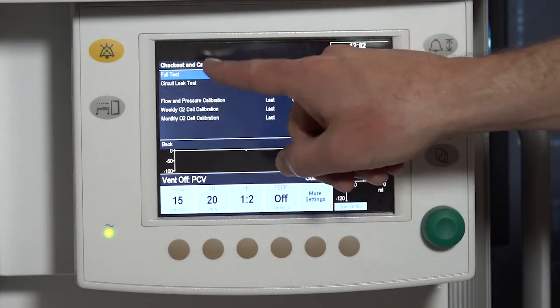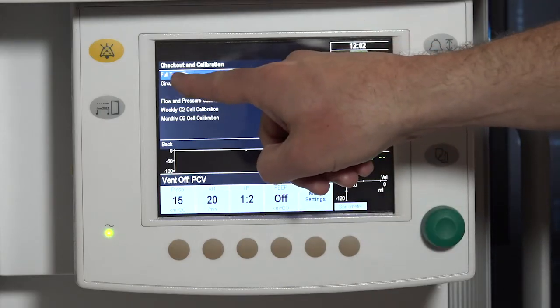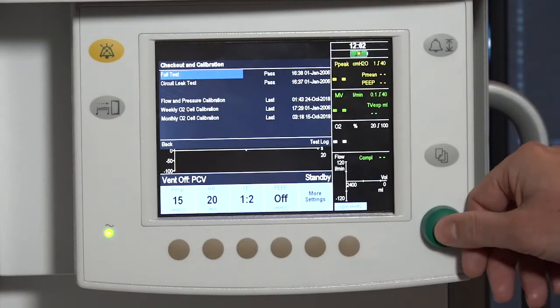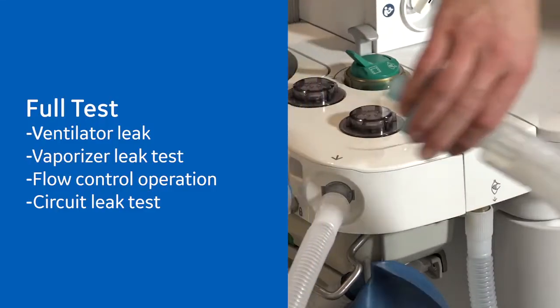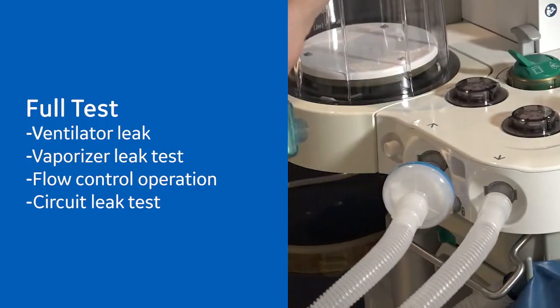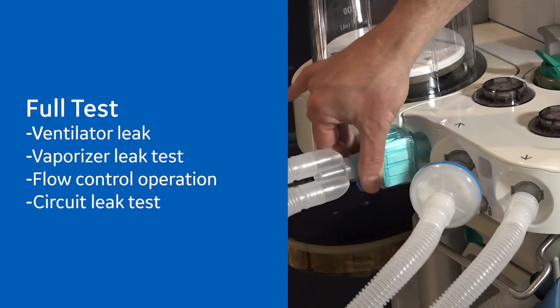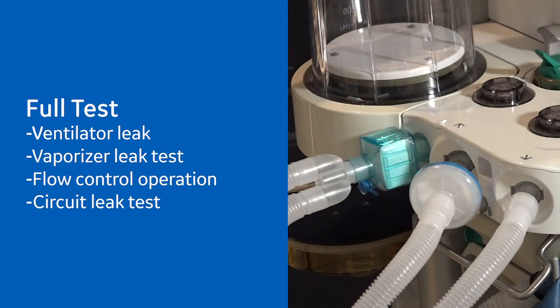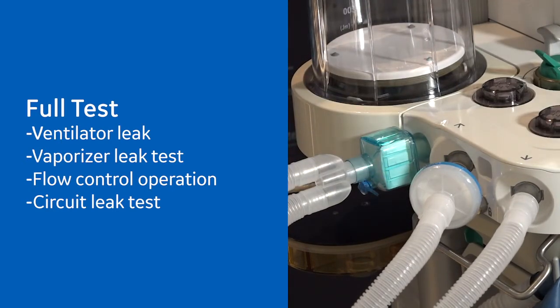Follow the on-screen instructions and select full test. The full test checks the ventilator leak, vaporizer leak test, flow control operation, and circuit leak test.